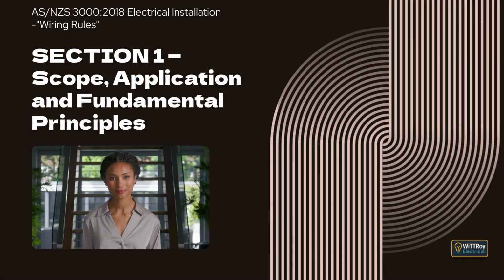A third method is electrical separation. This is normally done with a transformer that separates the output from earth, so there is no shock path if a single fault happens. The last method is limiting the fault current. In other words, if the design ensures the fault current is too small to be dangerous, then the risk of shock is very low. But in everyday electrical installations, automatic disconnection is by far the method we use the most.